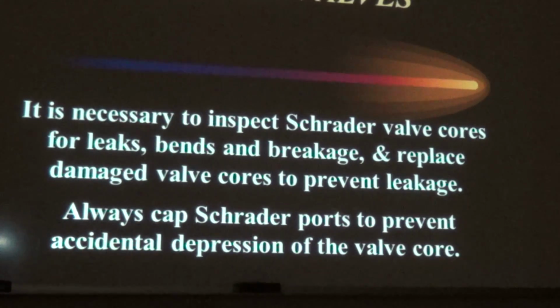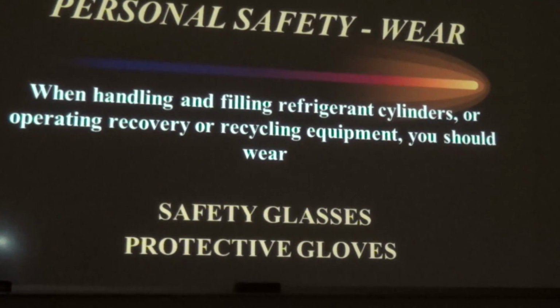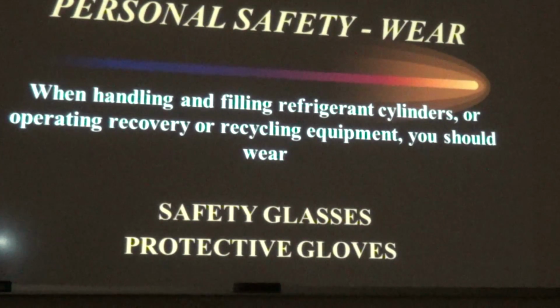Always cap a Schrader port to prevent accidental depression of the valve core and the leaking of refrigerant out of it. So when you go there and you work on the job, when you leave, by EPA rules, you have to make sure you put the screw cap back on. Also, personal safety gear. When handling, refilling, and filling refrigerant cylinders or operating recovery or recycling equipment, you should wear safety glasses and protective gloves.